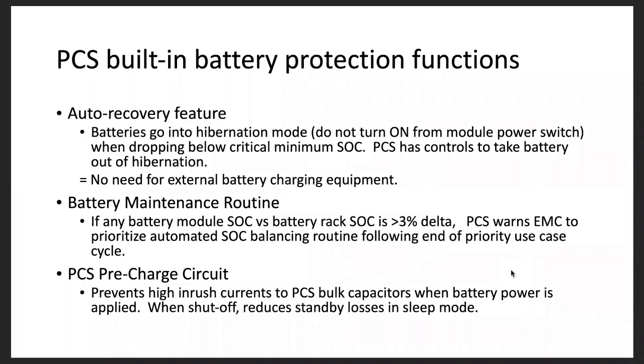So, some built-in PCS battery protection functions. As I mentioned a little earlier, there is an auto recovery feature where if the batteries go into hibernation mode when dropping below a critical minimum SOC, the PCS has controls to take the battery out of hibernation, and there's no need for external battery charging equipment. This note here is to not turn the battery on from the module power switch. This is just a side note for people who are service oriented: if the batteries have been shut down, you don't need to turn them on from the battery module switch; the auto recovery feature will turn the batteries on automatically.